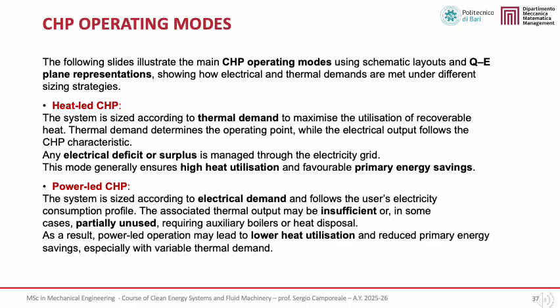This configuration generally results in high thermal utilization and is often favorable for achieving high primary energy savings. Conversely, when the system is sized according to electrical demand, the configuration is referred to as power-led CHP. Here, the CHP unit follows the user's electricity consumption profile. Residual thermal demand must be covered by conventional thermal technologies, such as auxiliary boilers.